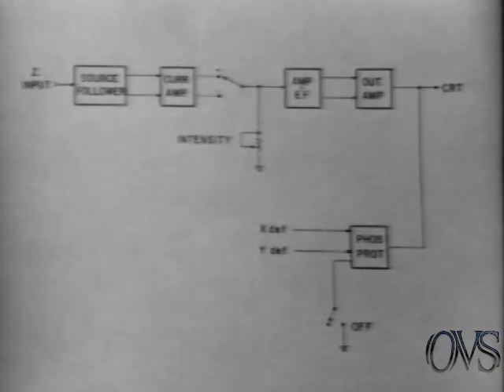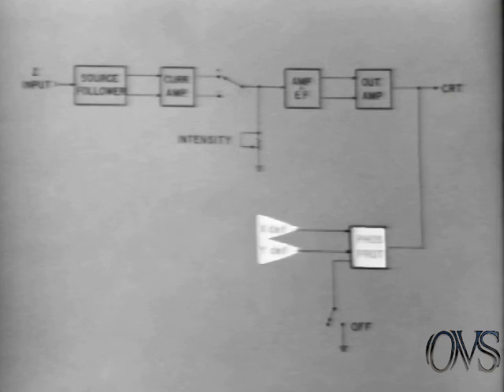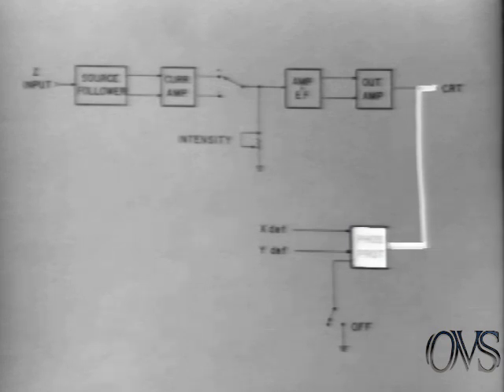Another input to the Z-axis circuitry is from the phosphor protection circuit. This circuit monitors the outputs of the X and Y deflection amplifiers and operates similar to an OR gate. One of these two inputs must always be present to keep the phosphor protection circuit in an inactive state. If there's no deflection on either axis, indicating a stationary beam, the phosphor protection circuit will activate and limit the Z-axis output level to prevent CRT burns. An on-off switch, located here, allows the phosphor protection circuit to be disabled. However, in normal applications, this is not recommended.